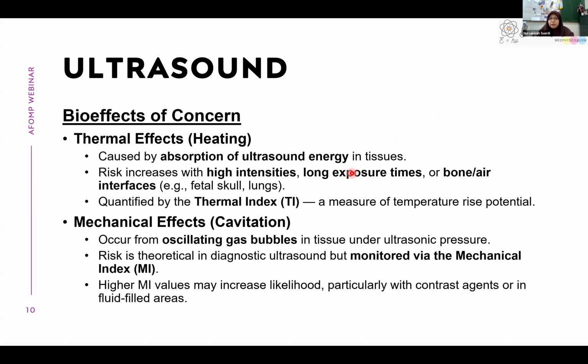So some of the biosafety concerns of ultrasound are, first, the thermal effects, which involve heating through the absorption of ultrasound energy in the tissues. The risk increases with high intensity, long exposure time, and if it interacts with bone and air interfaces, for example the fetal skull and also the lungs. These thermal effects are quantified by the thermal index, which is a measure of the temperature rise potential. The second effect is the mechanical effect, which involves cavitation. It occurs from oscillating gas bubbles in tissue under ultrasonic pressure. This risk of cavitation is monitored through the mechanical index. So higher MI values may increase the likelihood, particularly with a contrast agent or in fluid-filled areas, for example if you try to image the lungs.